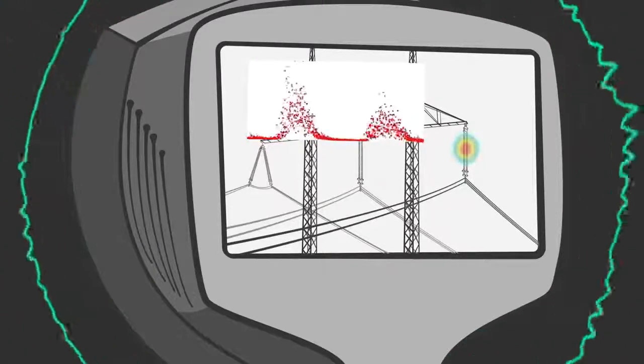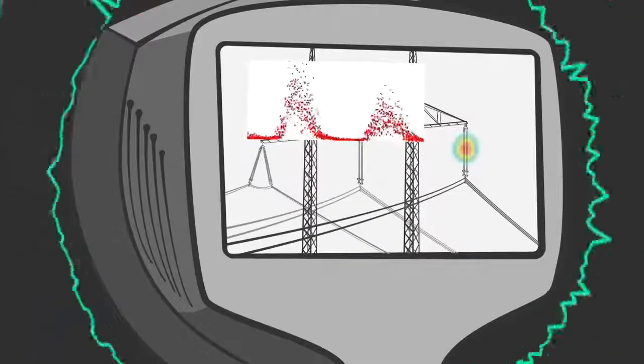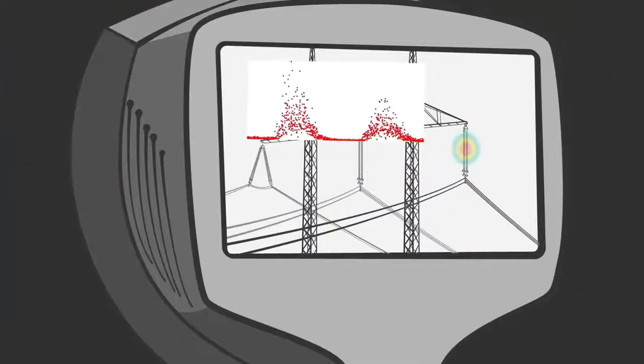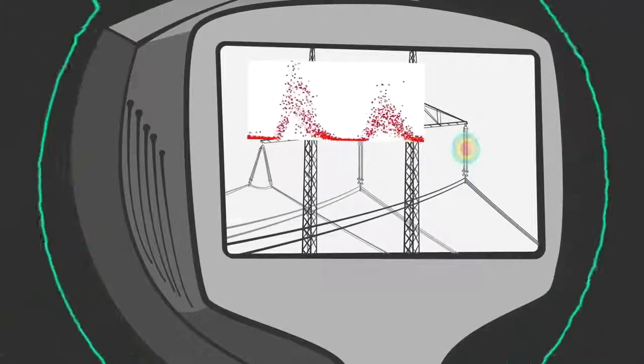By analyzing the sound from the partial discharge, the camera will show the phase-resolved partial discharge pattern, or the PRPD, which depicts the behavior of the discharge. All of the partial discharges behave differently and have their distinct discharge pattern.